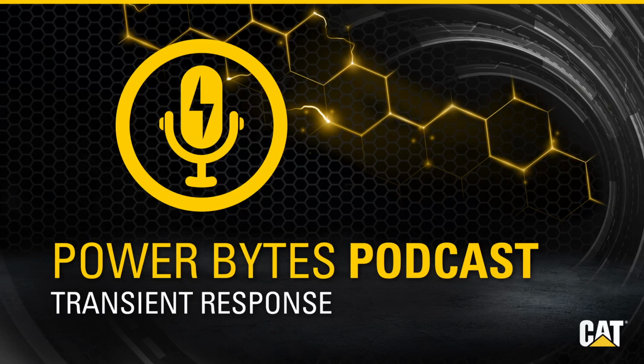So is it possible, Bryan, for you to explain what is happening in the engine when a transient occurs? Sure. This is often done better with visuals, but if you can imagine, an engine is operating with a specific amount of fuel and air supplied to the cylinder to produce the necessary power to support the steady state load. This is called the brake mean effective pressure, the BMEP. When a large load is added to the generator, the power being produced under the steady state operation can no longer support the demand from the load, and the speed begins to slow. To increase the BMEP, the engine applies more fuel.